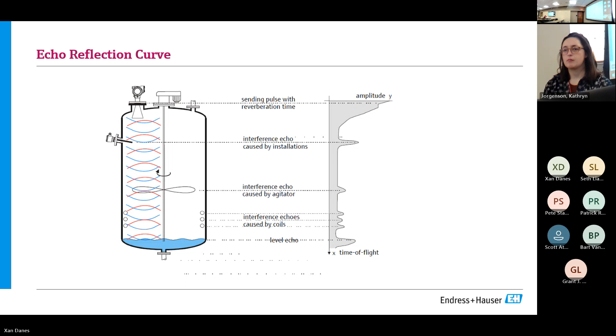Also want to point out that time-of-flight pulse-based radars physically look different from a frequency-modulated continuous wave radar. When I talk about that electromechanical bullwhip or impulse that generates that microwave signal launching a pulse down into the tank, I can actually see that in the near field—that's the orange area on the plot. So on the left, you can see where that signal impulse gets generated, up in the head of the transmitter. I can see how that looks over time.